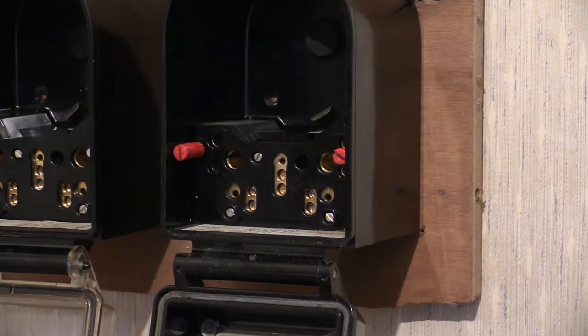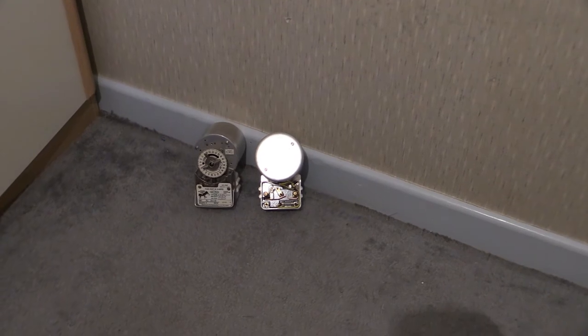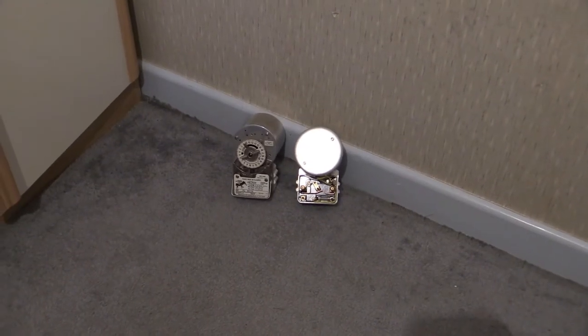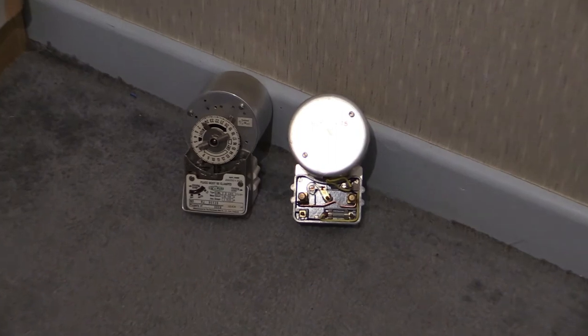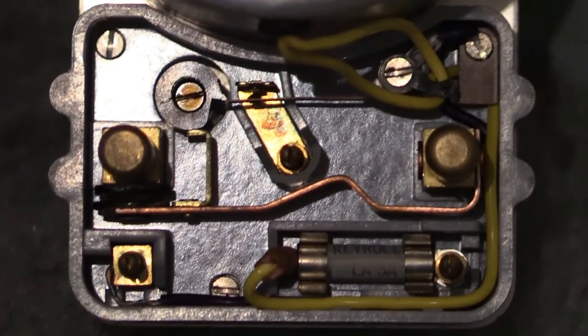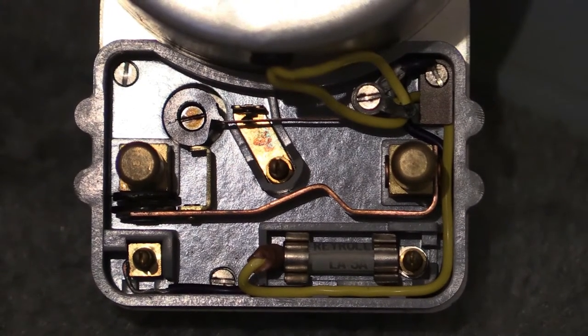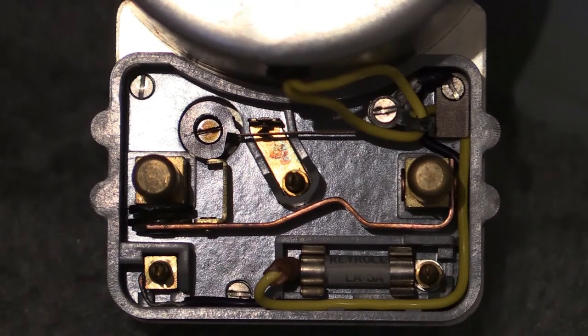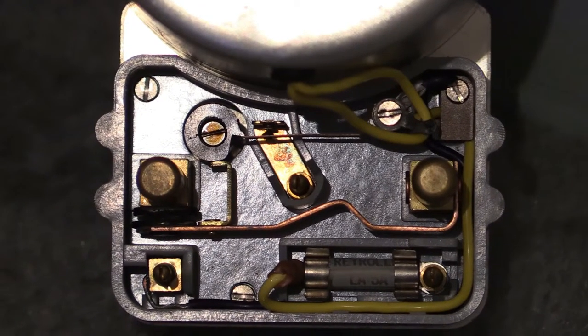Just down on the floor I have placed both the time switches, and we shall have a look at the pin base that's on them. I've placed one so it's facing towards us and the other one is facing against the wall. We shall be observing the one which is facing the wall. The terminal base on them is both the same. You can see at the bottom of the pin base there are two little wee skinny pins. That's for the synchro motor. Just up a bit from that, we got two big chubby pins, and they are for the big load, 80 amp loading capacity. There's a big old thick bus bar going between them.